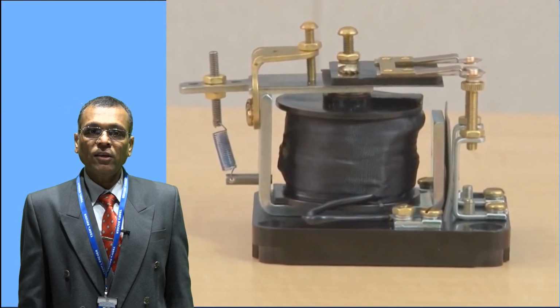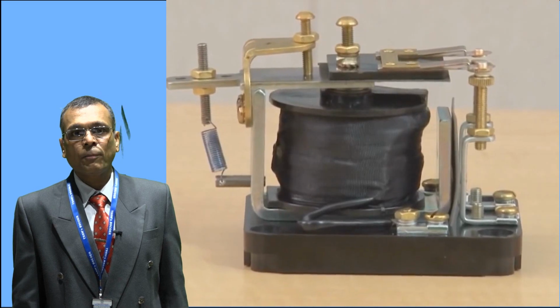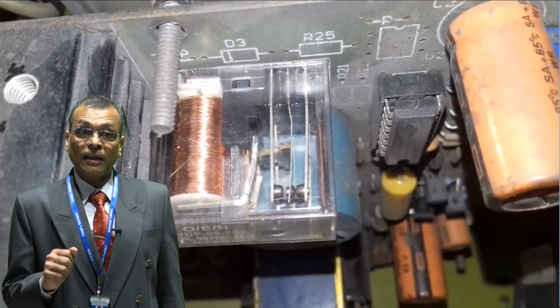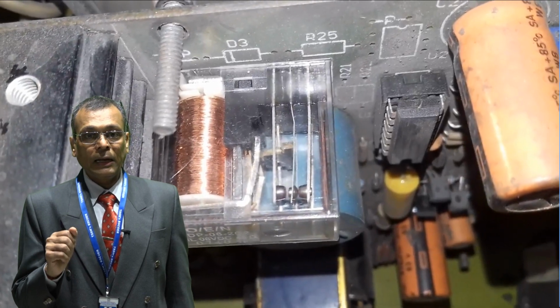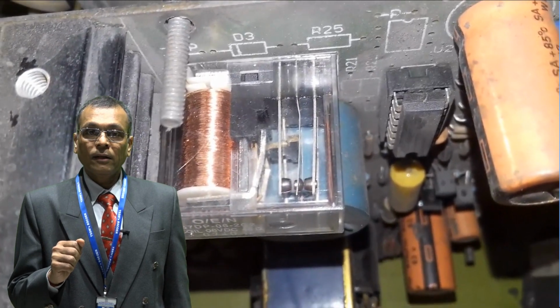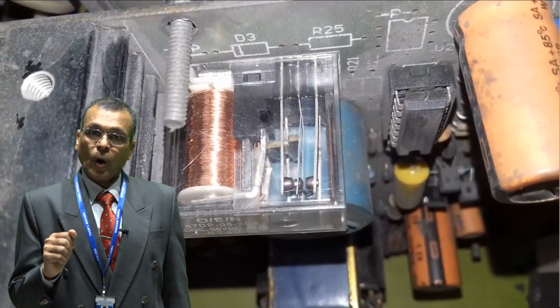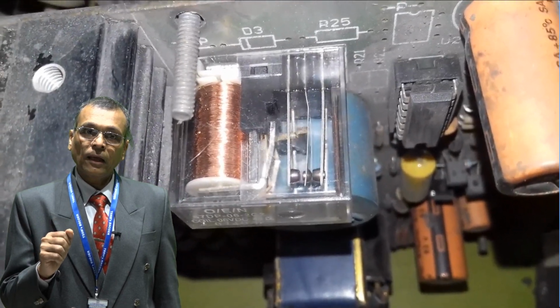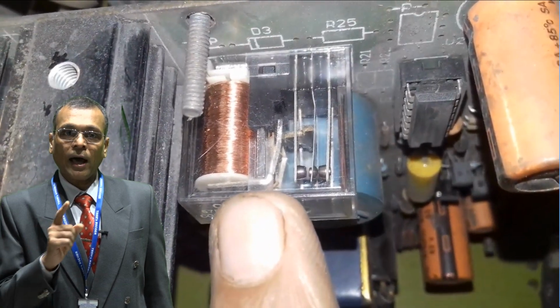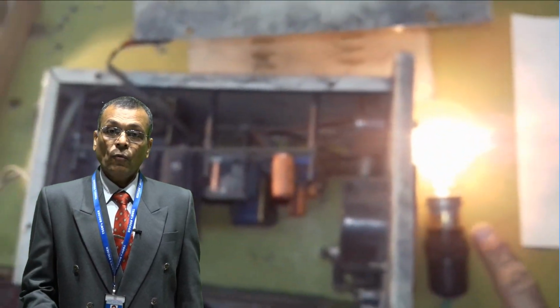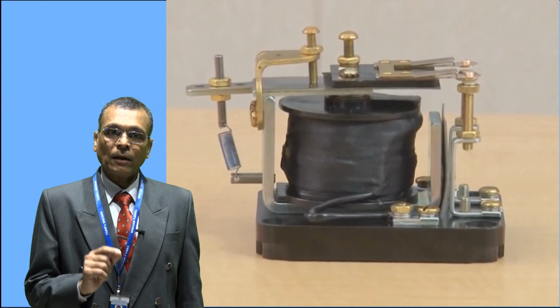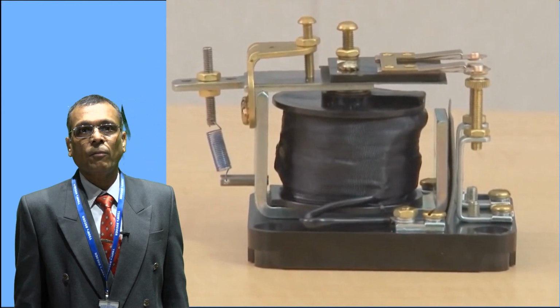Usually, a relay is used for field failure protection. The field circuit current flows through the coil of the relay, and the NC and NO contacts of the relay are used to connect the armature circuit and the DC supply. Thus, when the field fails, the armature gets disconnected from the supply.